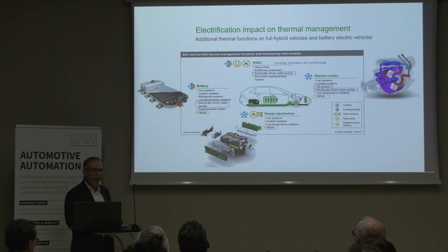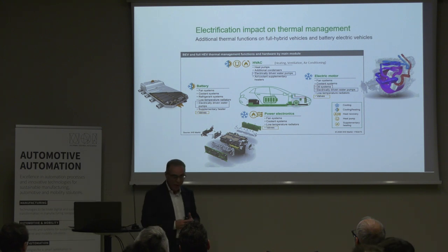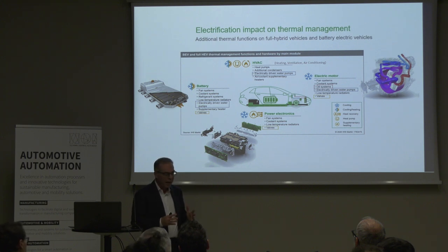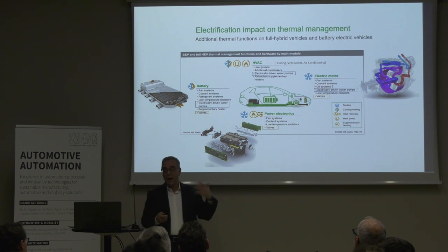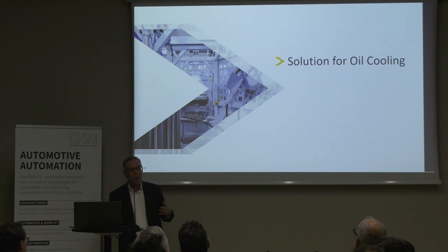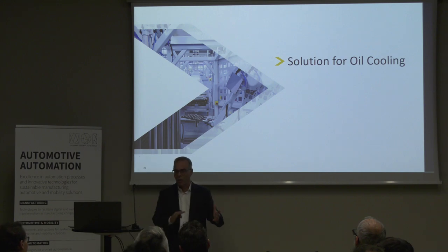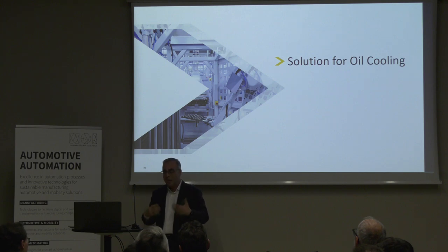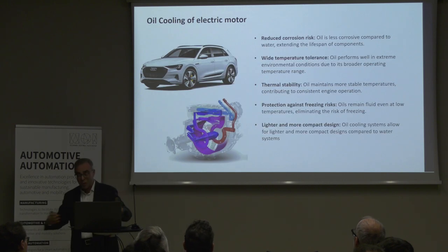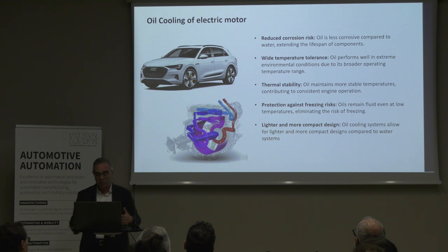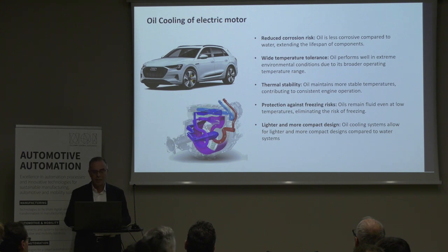With our components, so our technology, we have several ways of cooling. We mentioned air cooling, we have liquid cooling, and we are very strong in dielectric cooling and oil cooling, because basically our material is very oil friendly. With water glycol we are having some corrosion problems, so we are really specialized in oil cooling, and we are pushing it a little because you don't have corrosion, you have a very wide tolerance of temperature, oil is always performing well, and then of course there are other side advantages like protection against freezing, and you can have a more compact design.